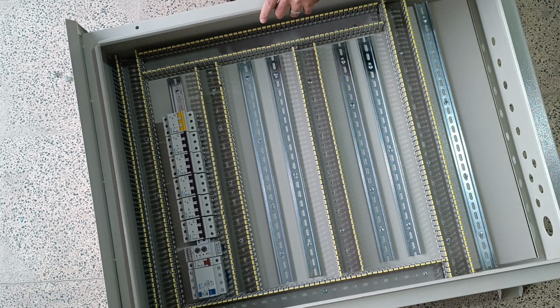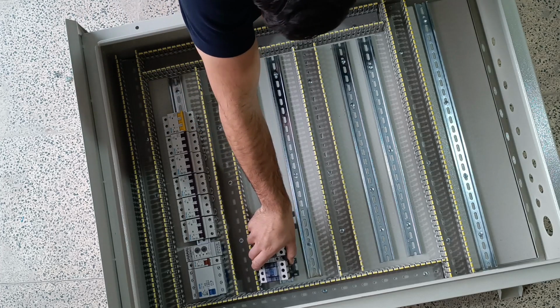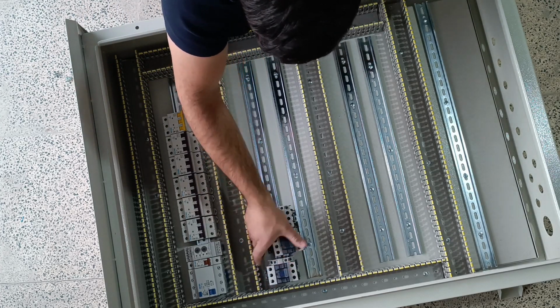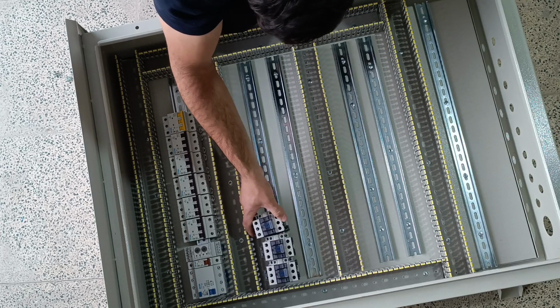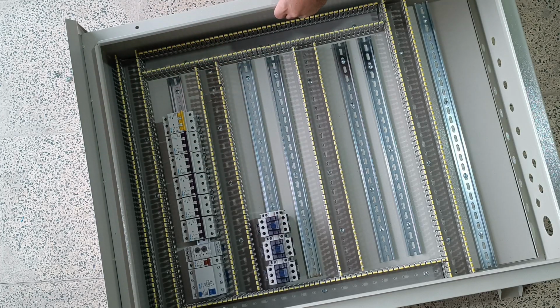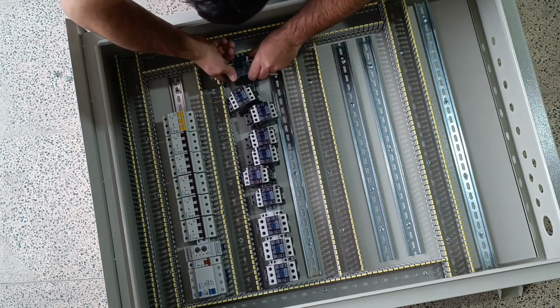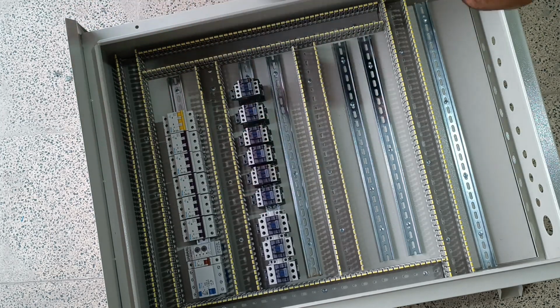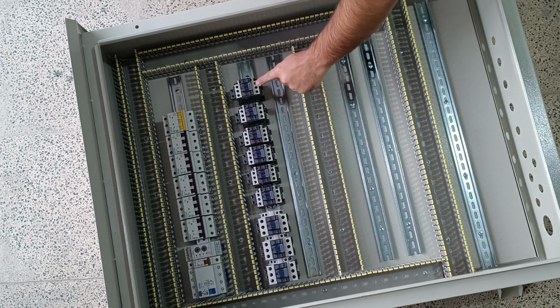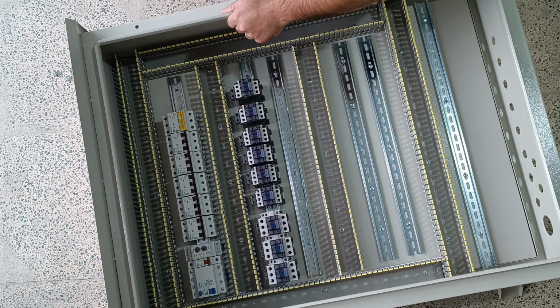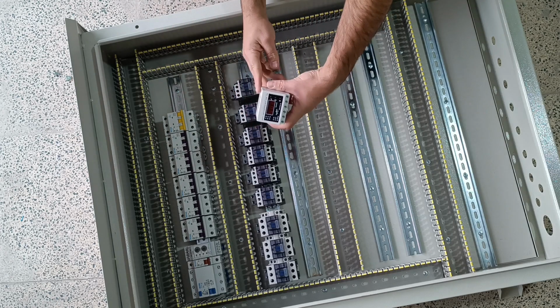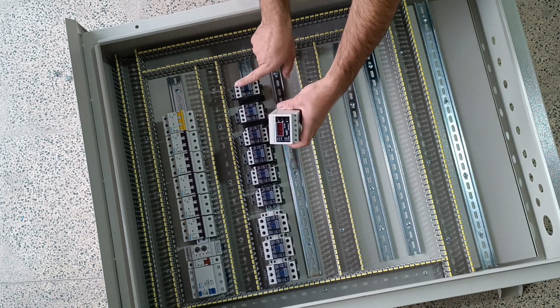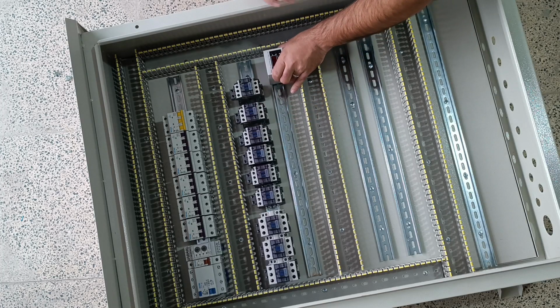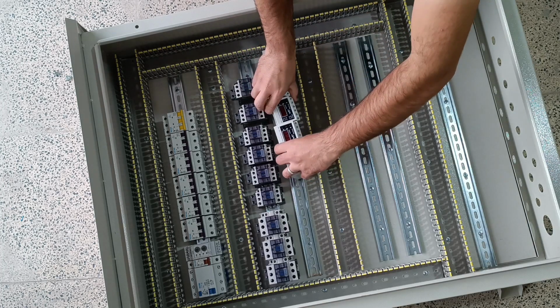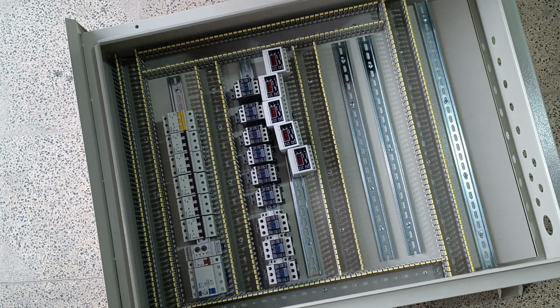Now we install 10 contactors for 3-phase outputs. Each 3-phase output needs one contactor to disconnect and connect. The contactors are magnetic switches and can be connected remotely. For each 3-phase output, I use a current controller relay, each of which is installed under its own contactor. This relay measures the output current from each contactor, and if excess current passes, it cuts off the circuit and avoids damage to the equipment.